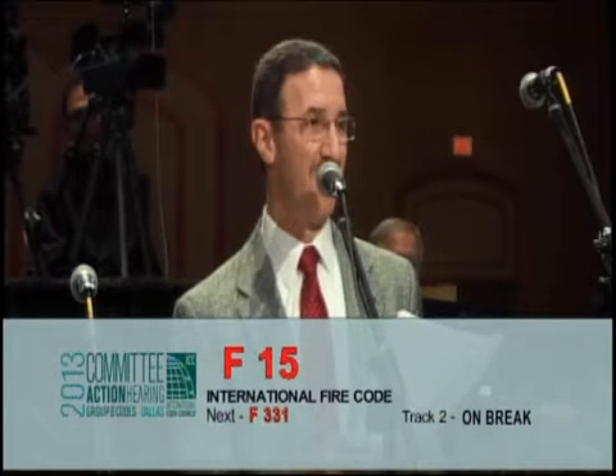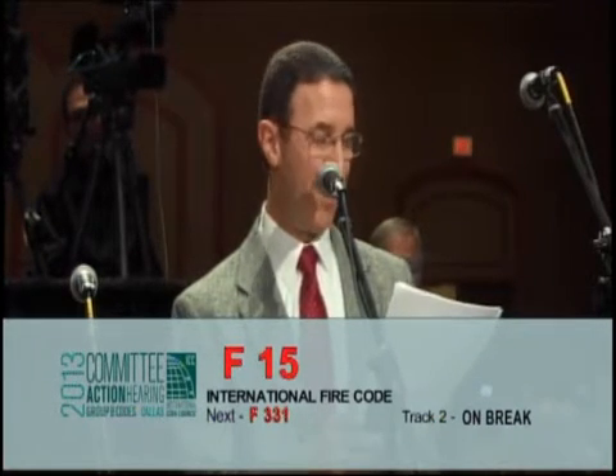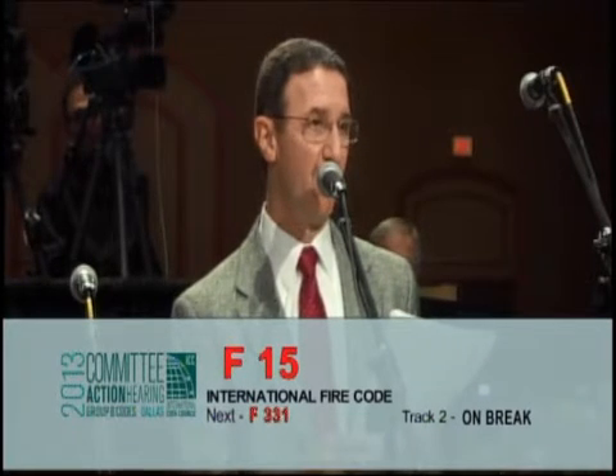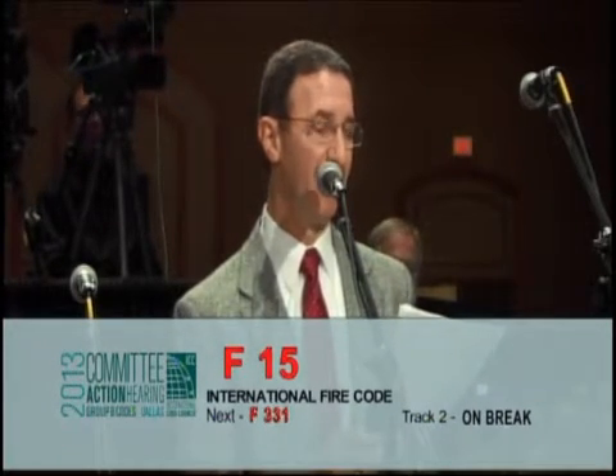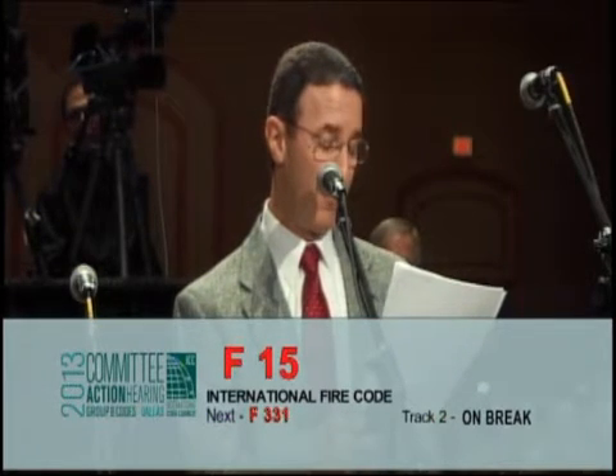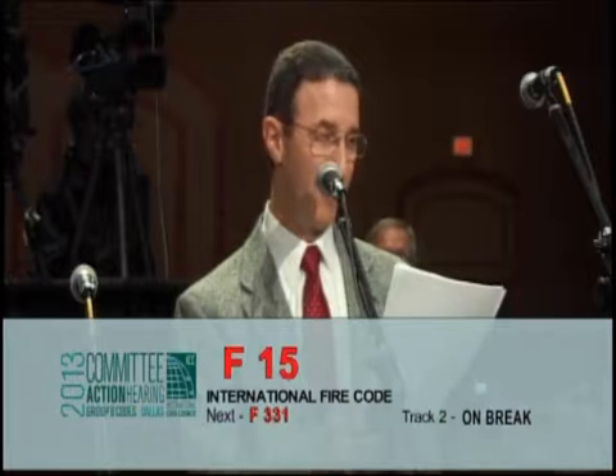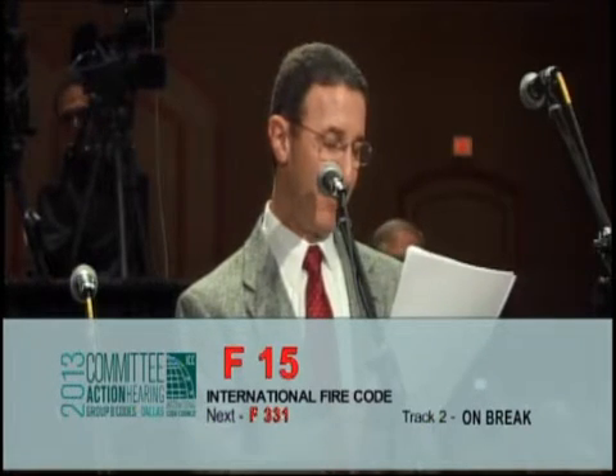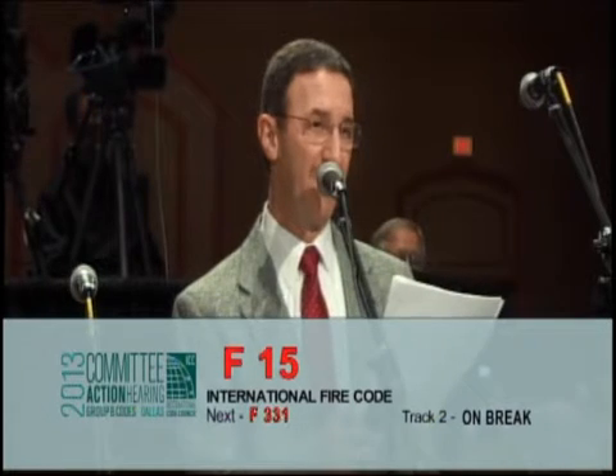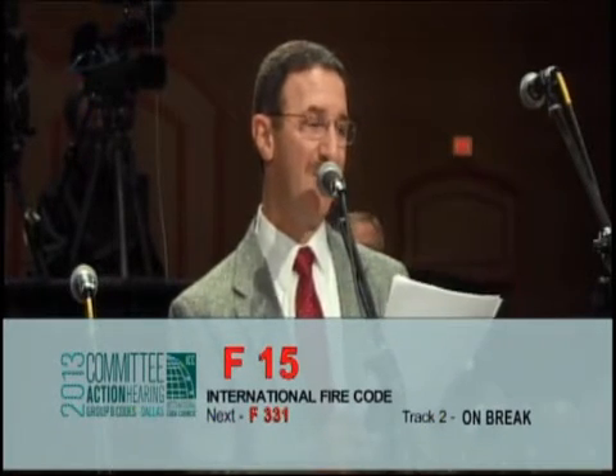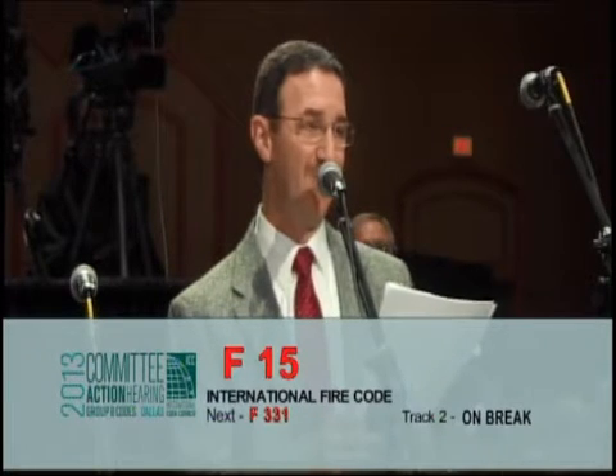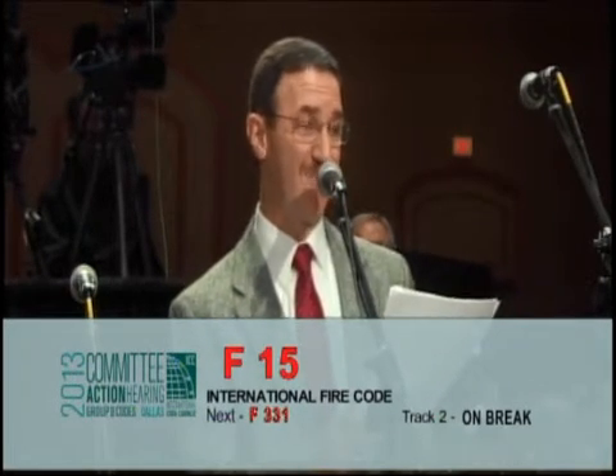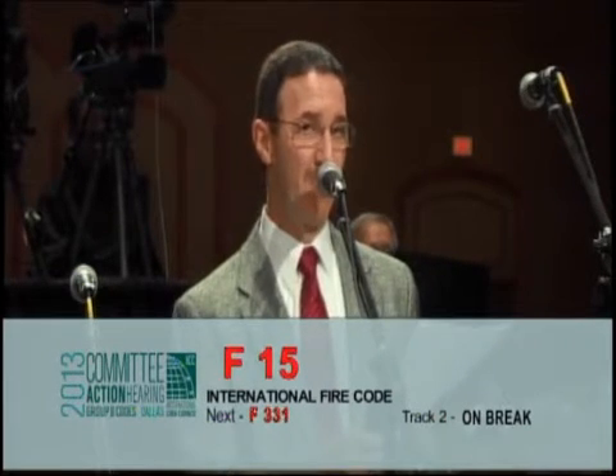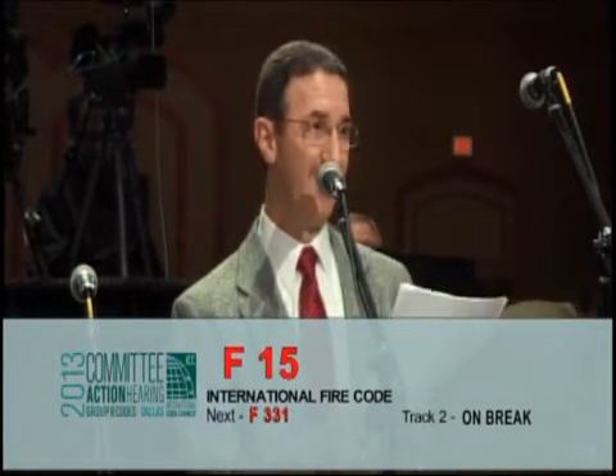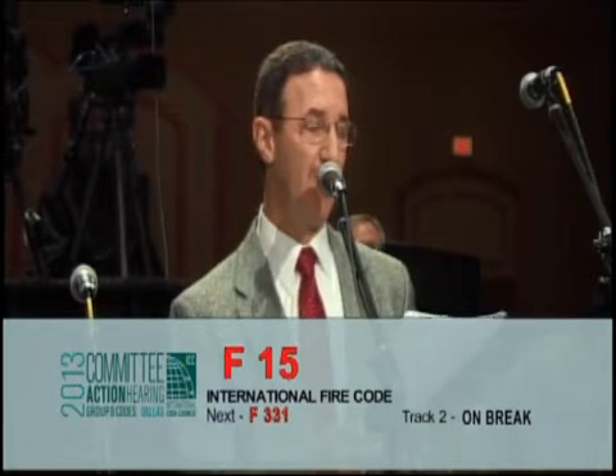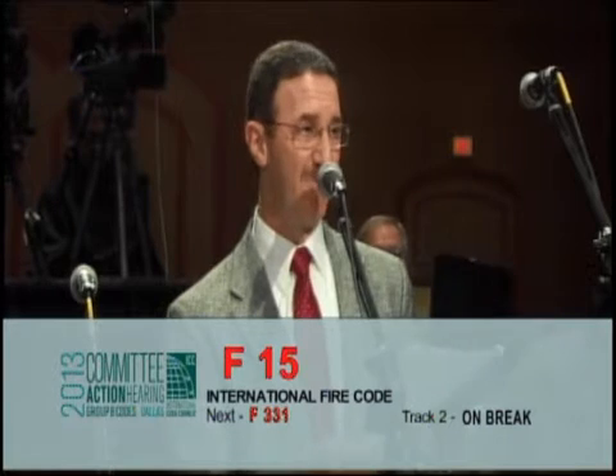And the answer is there was none. In fact, what would pass 312.3 could fail 312.2, so it didn't even meet the prescriptive requirements for posts. What the FCAC attempted to do with this was to create an alternative that doesn't go under alternative methods and materials, because there are many things in that section that are irrelevant to a bollard. There's not really a fire safety aspect of a bollard. Many of the things you have to list to show equivalency are not related to this issue. The other thing is, in many cases, the bollard design is not necessarily just an equivalent alternative method.